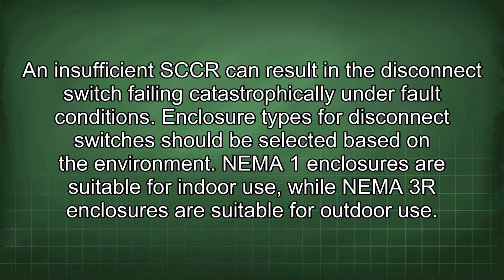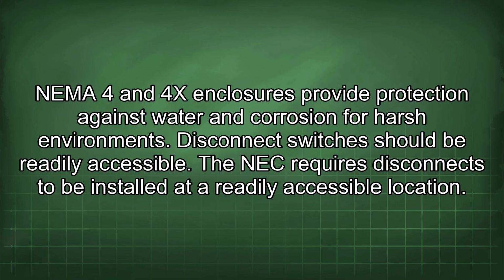Enclosure types for disconnect switches should be selected based on the environment. NEMA 1 enclosures are suitable for indoor use, while NEMA 3R enclosures are suitable for outdoor use. NEMA 4 and 4X enclosures provide protection against water and corrosion for harsh environments.